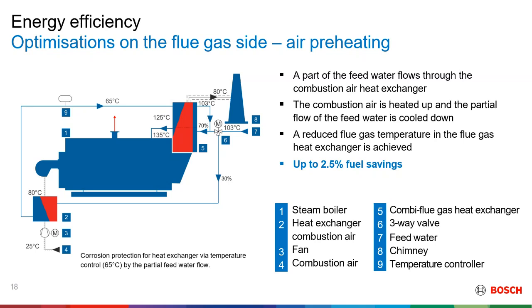The benefits of using an air preheater in this setup is once you have cooled down the water around 30%, you have dropped down the temperature from 103 to 65 degrees. Thereby, you have reduced the feed water temperature. With that, you have increased the gradient for heat transfer. Therefore, you're able to extract more heat with the economizer. And again, another benefit is you're able to heat up the air that is flowing into the boiler.